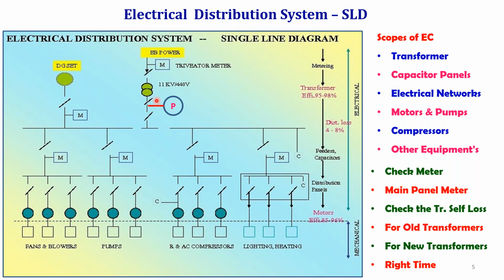So apart from that, we have a panel board meter. Most of the industries will have their own panel board meter. And top companies, or even most of the companies, measure the panel board meter at regular intervals, and they will also correlate it with the reading available in the main meter. The difference between the main meter and the panel board meter is the energy consumed by the transformer, or ultimately you can say it is the transformer loss.